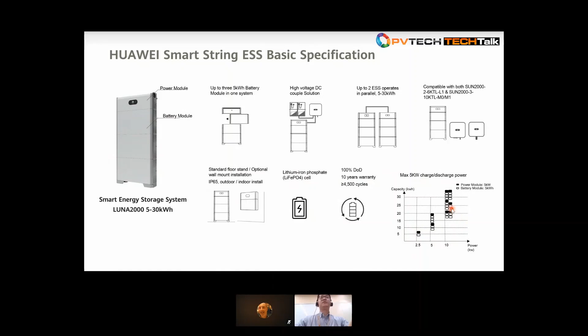And for the combination, because this is a modular design, it's very flexible. The smallest system will be a 5 kilowatt hours capacity, but with 2.5 kilowatt charging and discharging. And we can expand the capacity to 10 or 15 kilowatt hours with charging and discharging power up to 5 kilowatt. And we can get it even larger, from 20 kilowatt hours to 30 kilowatt hours, with the charging and discharging power at 10 kilowatt. So that's some basic information on Huawei's ESS.